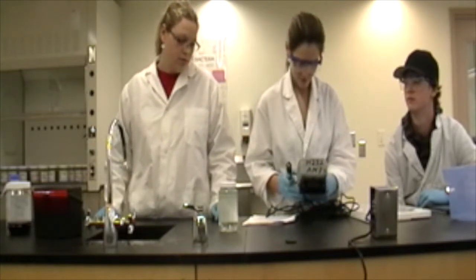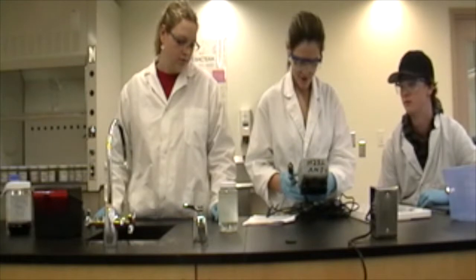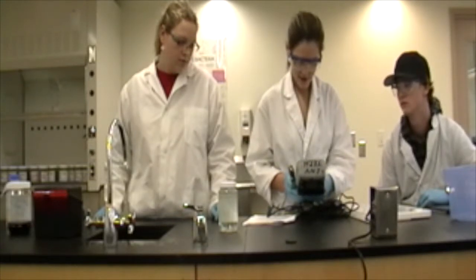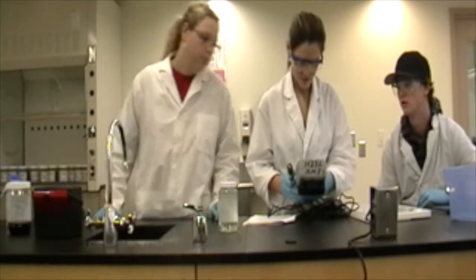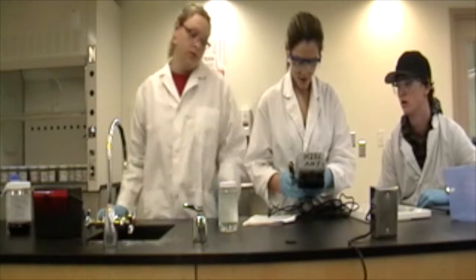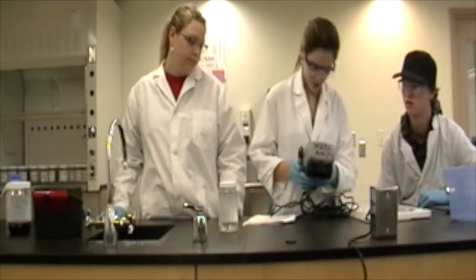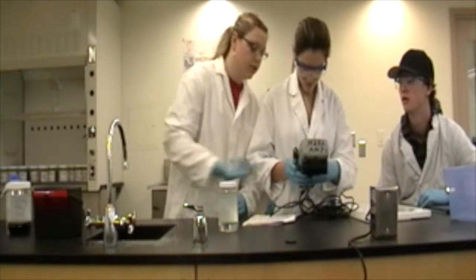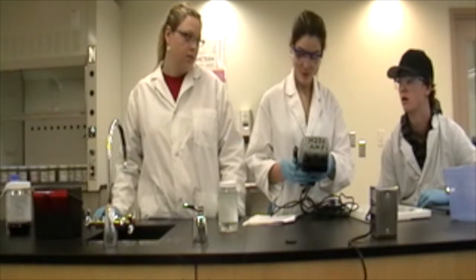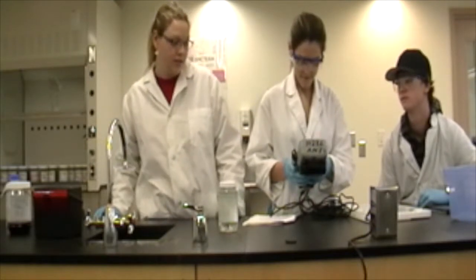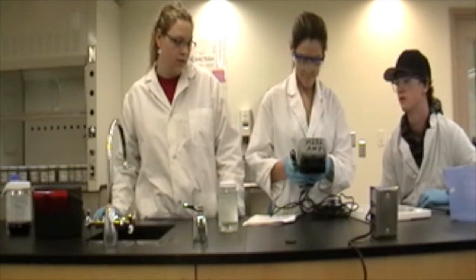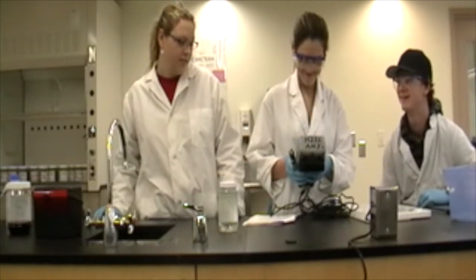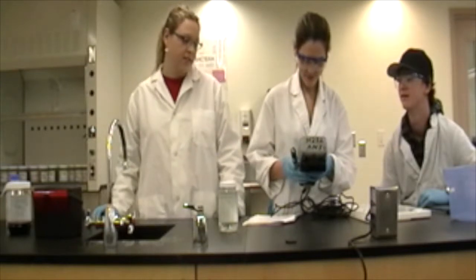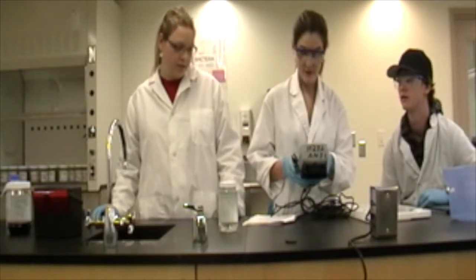Shoot. What happened? Okay, we're going to do that again. You guys were too hasty with the button pressing. It is off and then on. Up and down arrows at the same time for calibration mode. Enter. Change it from percent to milligrams. I know, but I have to click enter first. Oh no, you're totally right. What are you doing? Just change it. There you go. And then enter. Yes. After you hit milligrams per liter. Yes. It's 8.6. What do you mean? 8.6, enter. Salt is at 0 because we have fresh water.